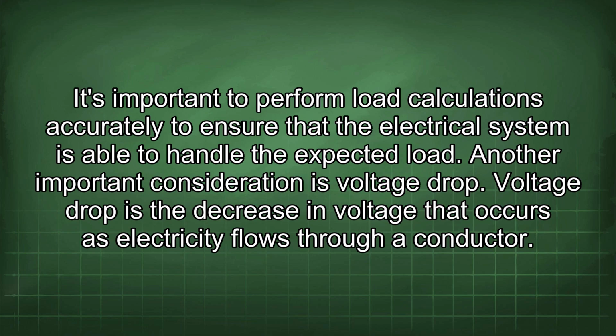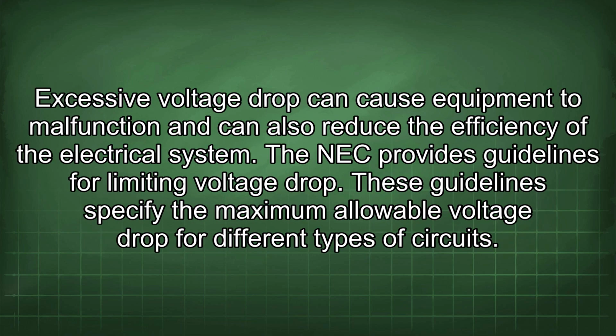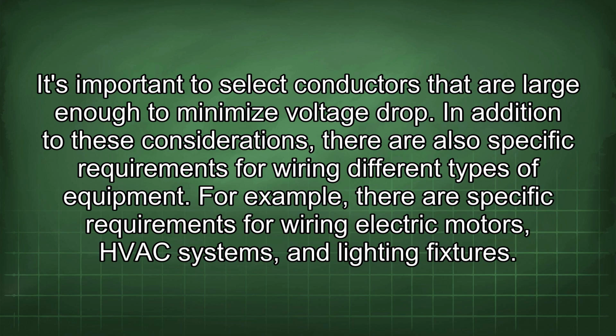Voltage drop is the decrease in voltage that occurs as electricity flows through a conductor. Excessive voltage drop can cause equipment to malfunction and can also reduce the efficiency of the electrical system. The NEC provides guidelines for limiting voltage drop. These guidelines specify the maximum allowable voltage drop for different types of circuits. It's important to select conductors that are large enough to minimize voltage drop.